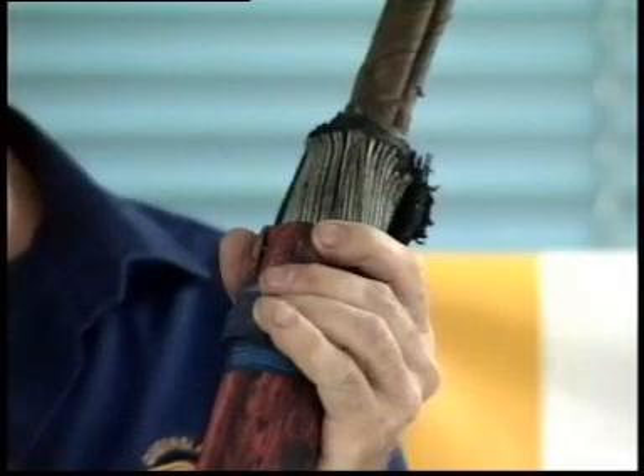If you are finding that that's happening, you've probably got something wrong with a main neutral or something in your system somewhere, and you should get it checked out, because the voltage is rising on the earthing system within your house. Now this fella here is supplying you 11 kV supply underground.